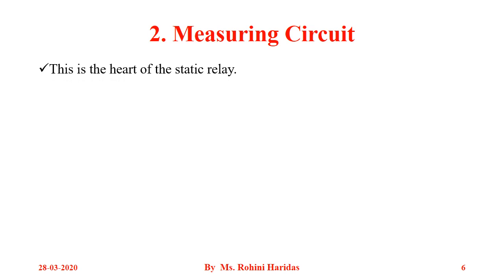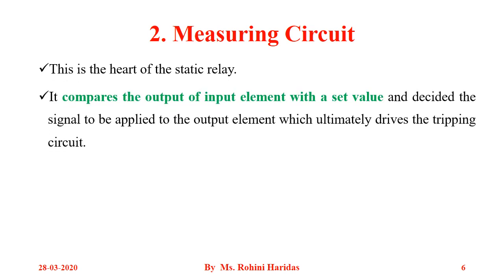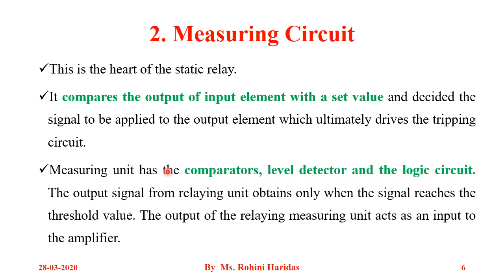Next is the measuring circuit. This is the heart of the static relay. It compares the output of the input element with the set value and decides the signal to be applied to the output element, which ultimately drives the tripping circuit. The measuring unit has comparators, level detectors and logic circuits. The output signal from the relaying unit is obtained only when the signal reaches the threshold value.